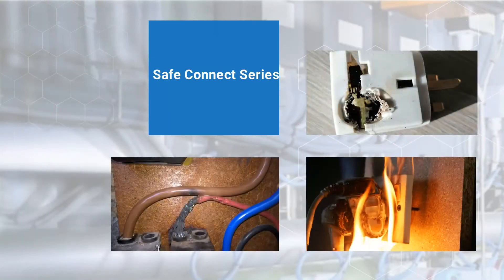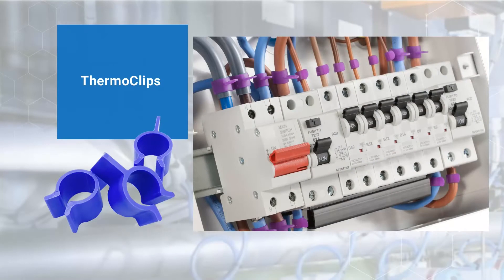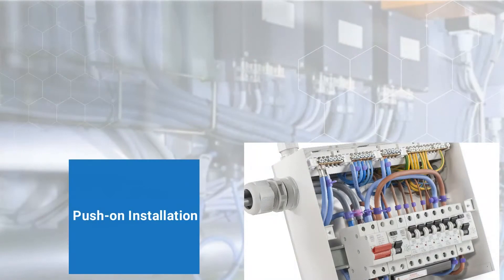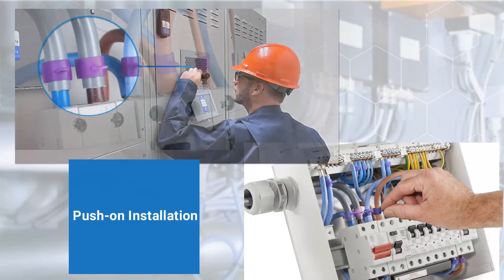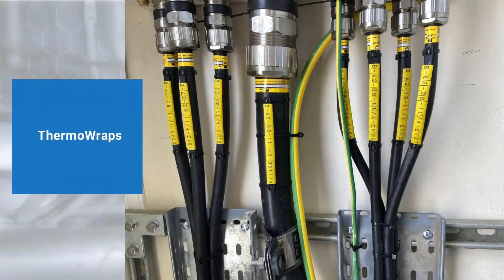ThermoClips serve as over-temperature indicators for electrical assets in both straight and non-continuous load applications, protecting against electrical fire or equipment failure. These easily installed clips require nothing more than a quick push onto cable connections, providing a predictive warning that is highly visible through any infrared window. With a memory effect feature, these non-conductive clips let inspectors see a permanent record of over-temperature excursions in intermittently loaded systems.